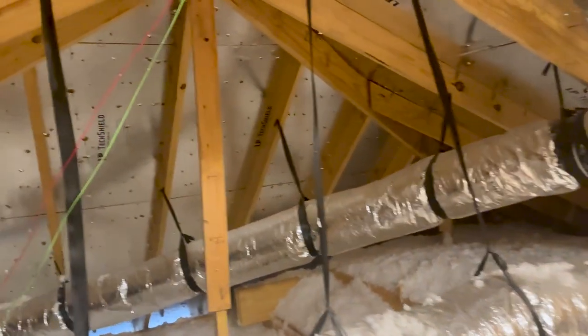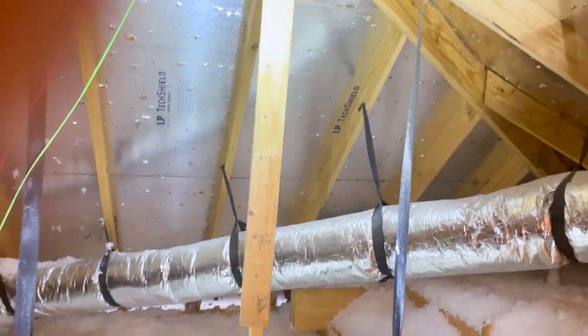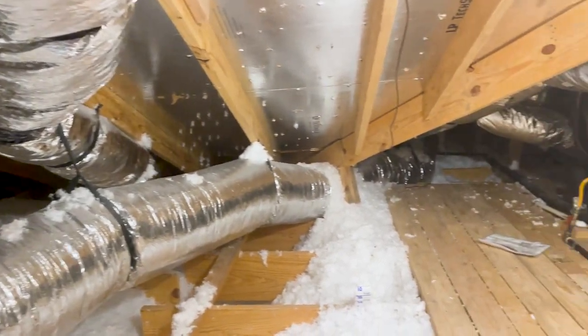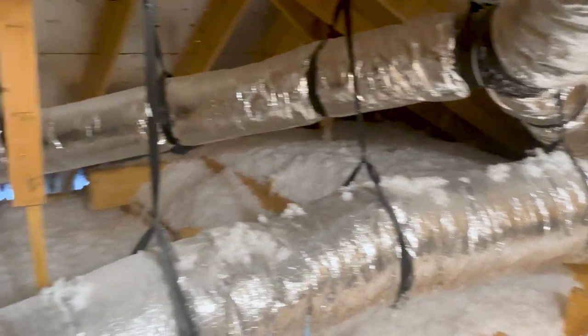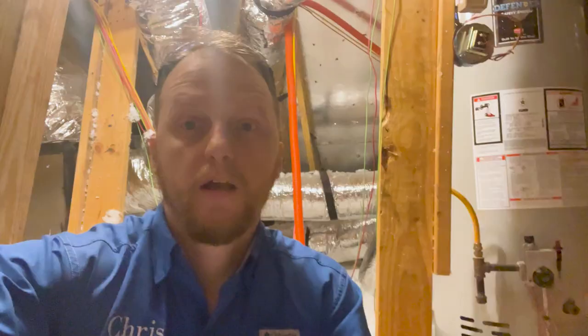The AC system is clean — the people are moving into a clean AC system, which you never see. That's a really good sign that this builder took extra steps to take care of the buyer. This isn't a find, but something to keep an eye on: pay attention to the ridge vents to make sure they're open. I can't tell you how many new builds we've inspected where they've sealed up the ridge vents and had poor airflow.